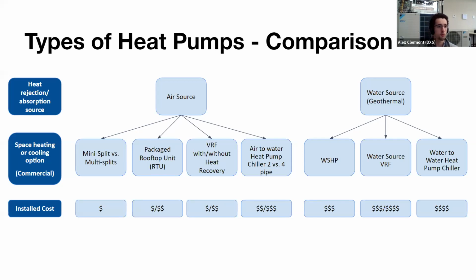Now, if we flip over to water source, assuming this is geothermal, water source heat pumps would be the most cost-effective option under water source. And then you'd have water source VRF, which again, depending on what you are doing in terms of heat pump or heat recovery and different kinds of indoor units, would also change that cost profile. And then on the pricier end would be the water to water heat pump chiller machines that we talked about as well.